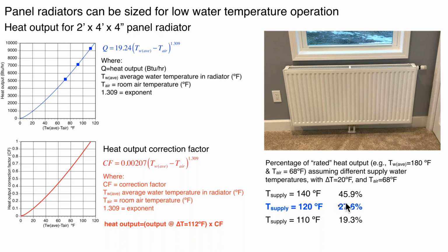I will tell you right down here that with a supply water temperature of about 120 degrees, you can see that you're going to get about 27% of what you would at 180 degrees. Okay, so how's that going to affect the design? You're basically going to need larger panels. And the lower the water temperature that you design these around, the bigger the panels have got to be. But 120 degrees supply temperature at design load is very compatible with these panels. These do not have to have high temperature boiler water. You simply have larger panels.